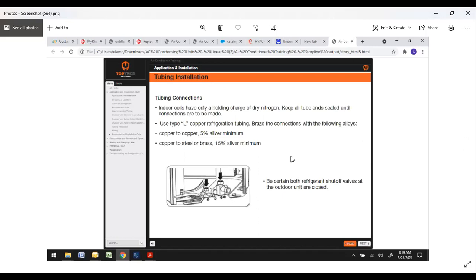Tubing connections, indoor coils. So when you get a brand new coil, you're going to have a slight holding charge of dry nitrogen. Keep all the tube ends sealed until your connections are made. Use type L copper refrigeration tubing. Braze the connections with the following alloys: copper to copper, 5% silver minimum; copper to steel or brass, 15% silver minimum. Be certain both refrigerant shutoff valves at the outdoor unit are closed. A lot of guys are using the press fittings, and they've even got some, I'll call them shark bites, but refrigeration shark bite fittings now. So you don't even necessarily need to use a torch to braze it shut.